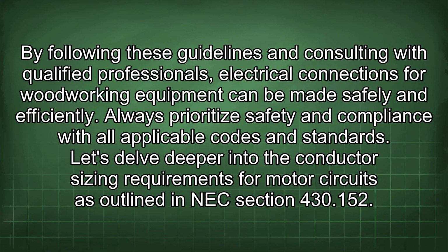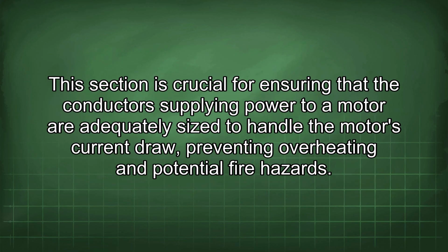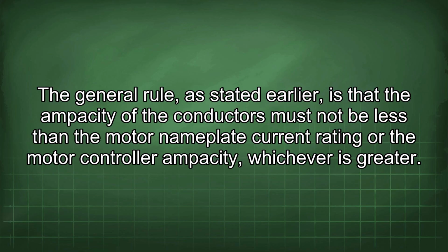Let's delve deeper into the conductor sizing requirements for motor circuits as outlined in NEC section 430.152. This section is crucial for ensuring that the conductors supplying power to a motor are adequately sized to handle the motor's current draw, preventing overheating and potential fire hazard. The general rule, as stated earlier, is that the ampacity of the conductors must not be less than the motor nameplate current rating or the motor controller ampacity, whichever is greater.